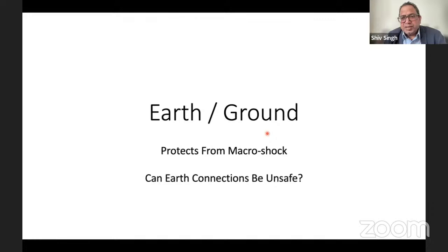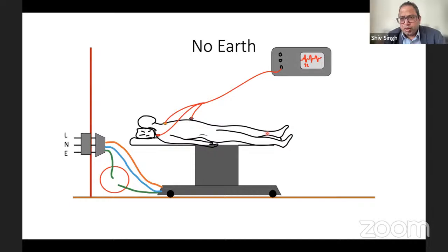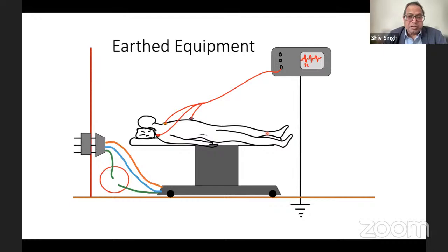So does earth become a danger? Yes, it does. And that's why it is not used in the supply in the hospital operation theaters. You have a patient who is connected to an ECG, lying on a table made of metal. If the equipment connected to the patient is now earthed, for example, you have an ECG machine with isolated power, but it is sitting on a trolley that is earthed, then you can actually get a shock. The patient can get a shock, and it can cause burns.